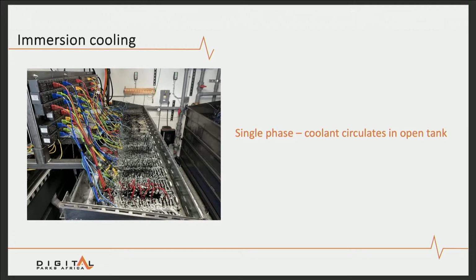So in an immersion cooling model, what you really see is two different technologies. The one is a single-phase technology, the other is called a two-phase technology. So the single-phase technology is a horizontal tank, as you see there, and the servers are inserted vertically into that tank, and the tank is filled with a very specialized, non-conductive, non-corrosive, non-harmful, biodegradable liquid with very good heat transfer properties. And that liquid essentially circulates throughout that tank to an external heat exchanger. So there's a low power pump that keeps the circulation of the liquid inside that tank going all the time.